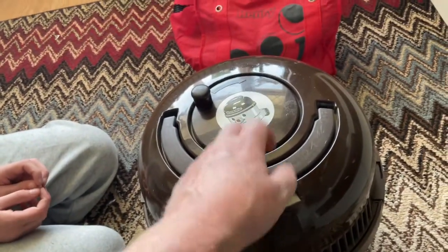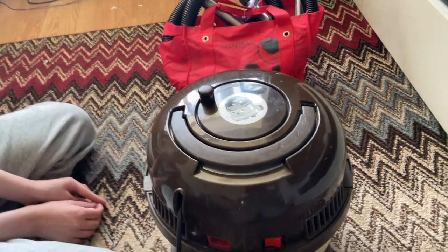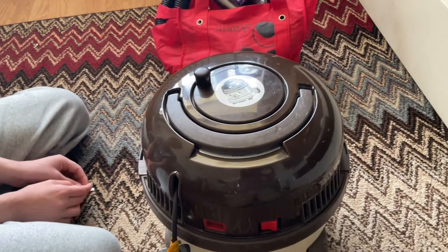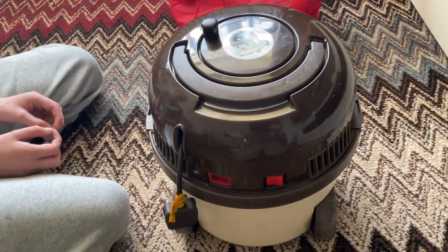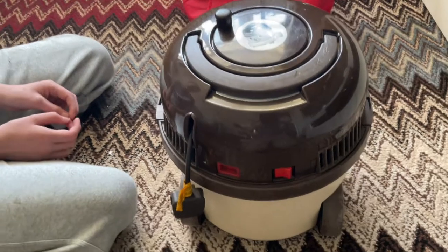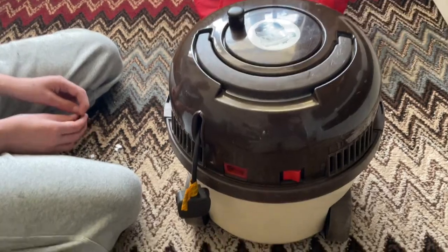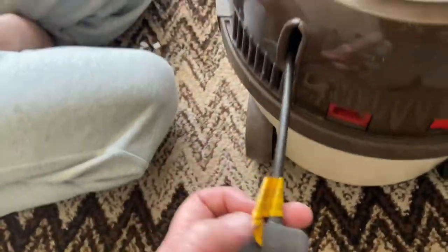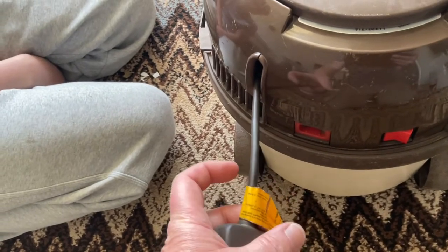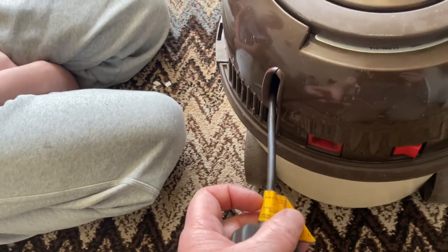On investigation, I do believe the suppressor went on it, and that's possibly why they sold it or sent it for recycling. I took that out and everything's been working well. When you're using it, did it trip? I think it did, yeah, just for a short while.